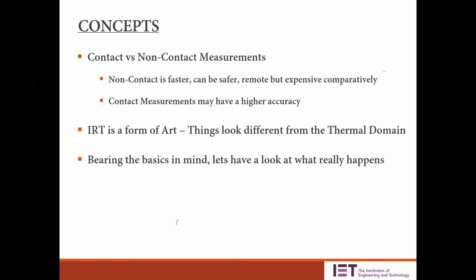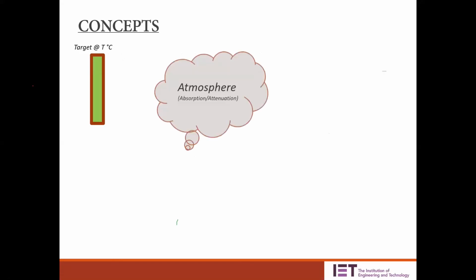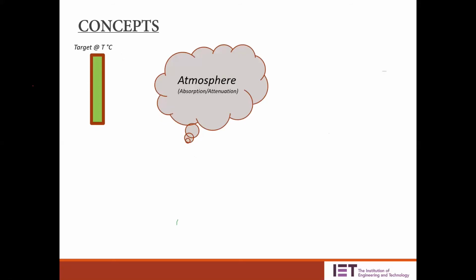Bearing that in mind, we'll move to more concepts. Say you have a target at T degrees Celsius—it could be a piece of metal, plastic, or anything heated to a temperature. You have the atmosphere around it, which absorbs the radiation and attenuates it, along with relative humidity and maybe some debris or smoke. And you have your instrument with you.